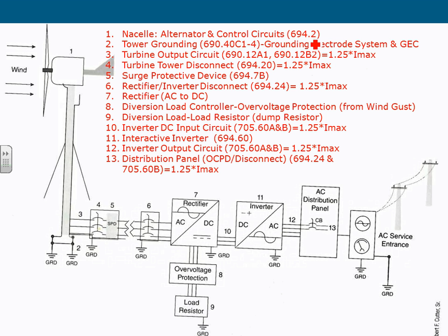So that's number two, ground, and we use the term grounding electrode system and grounding electrode conductor. So you have the system, and you tie the tower into that grounding electrode system. And sometimes the bolts themselves actually act as your grounding electrode conductor. Any comments, guys? Bringing the power from here through the wires down.